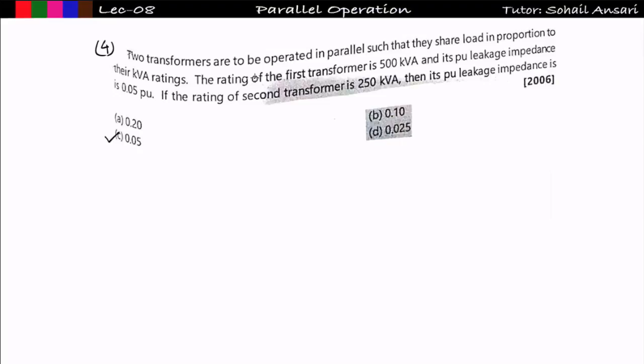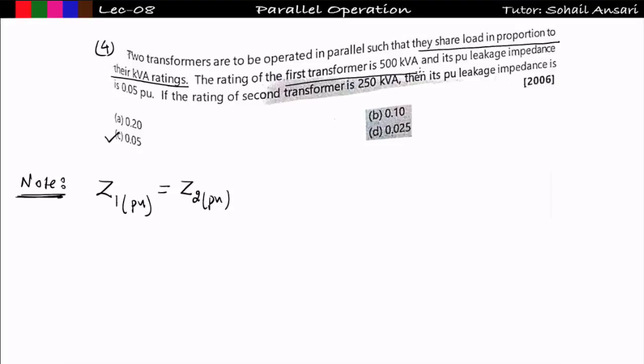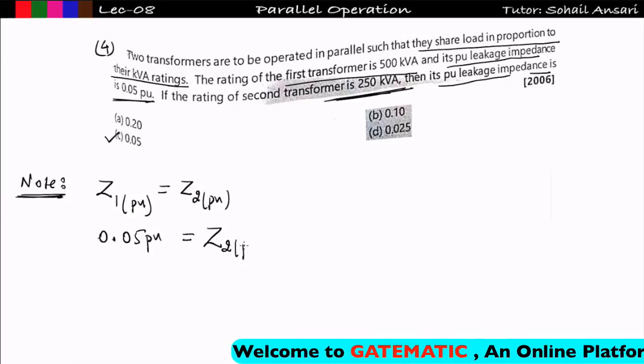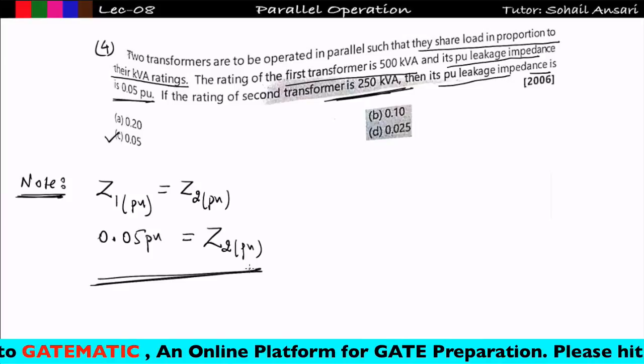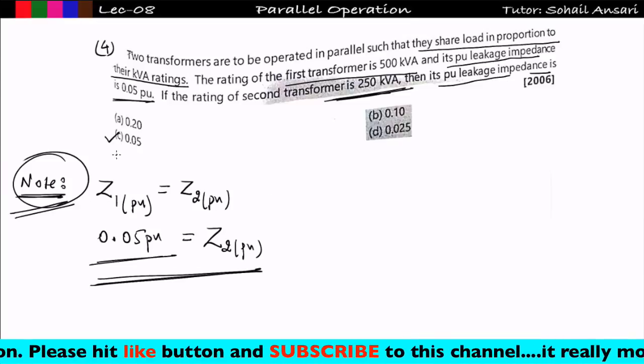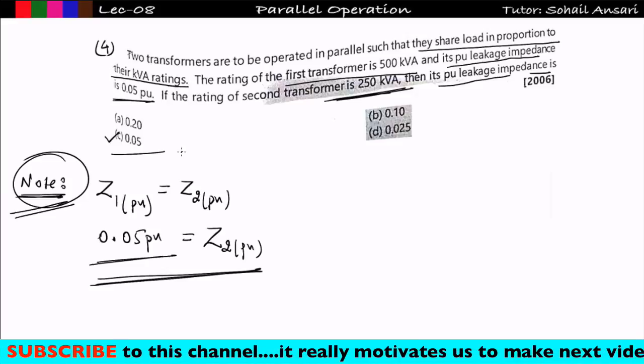The next problem asks: for two transformers operating in parallel to share load in proportion to their kVA ratings, what condition must hold? As explained in the previous lecture, the per-unit impedance of both transformers on their respective bases must be equal. Transformer 1 is rated 500 kVA with per-unit leakage impedance Z1_pu = 0.05 pu. Transformer 2 is rated 250 kVA. For proportional load sharing, Z2_pu must also equal 0.05 pu on its own 250 kVA base.